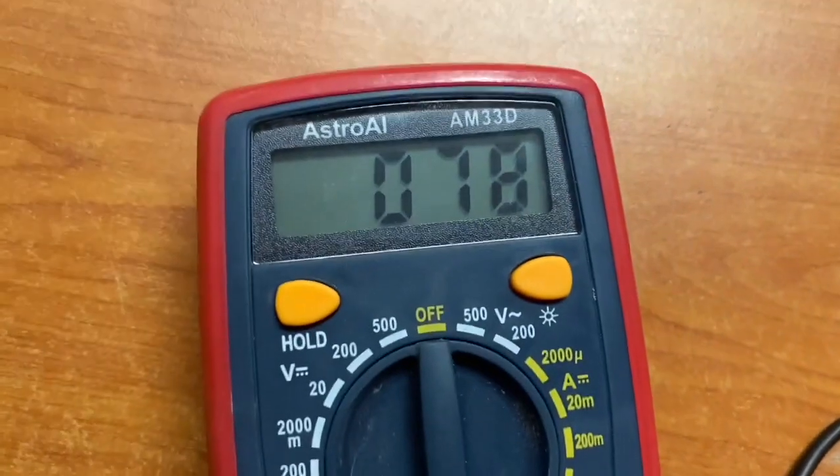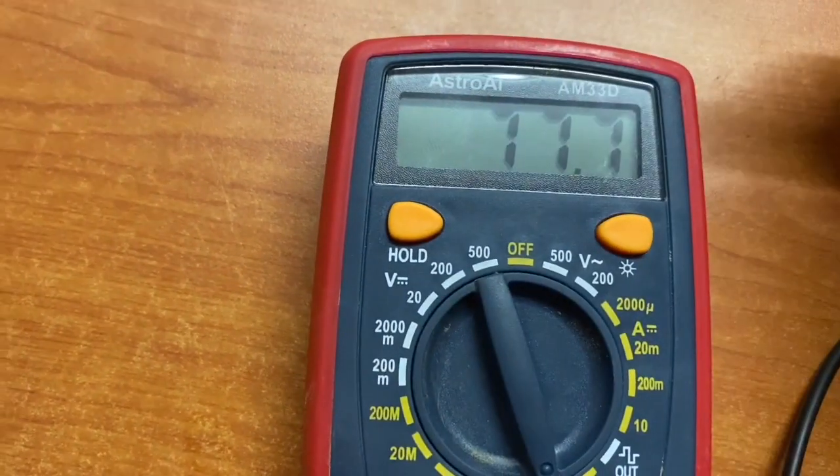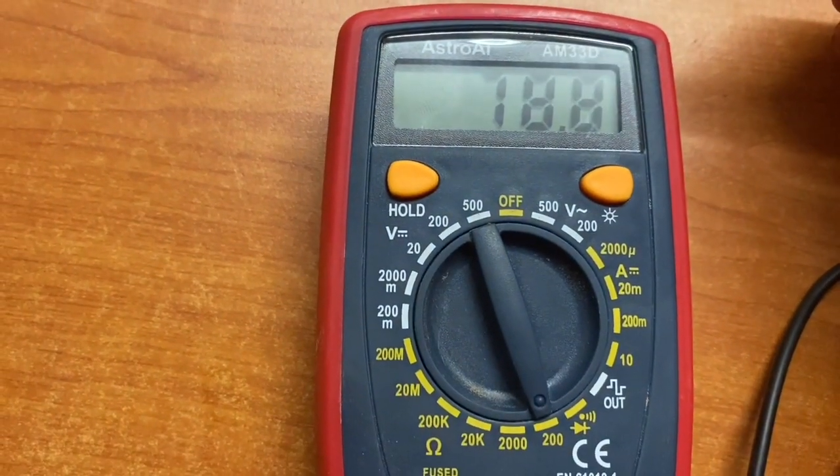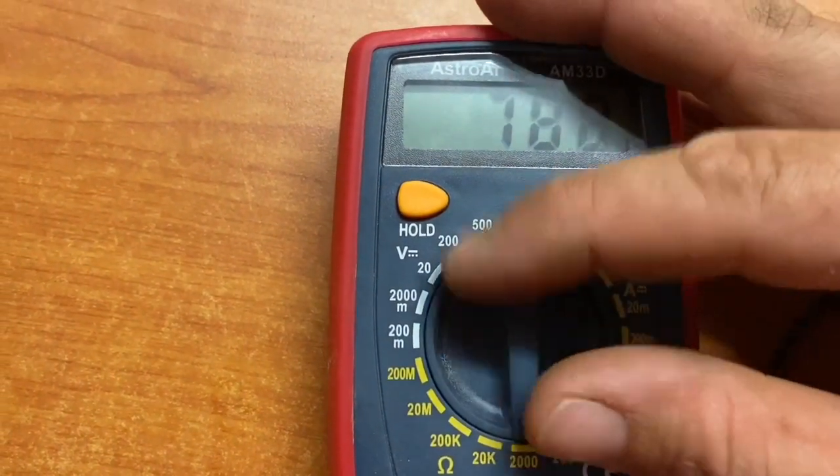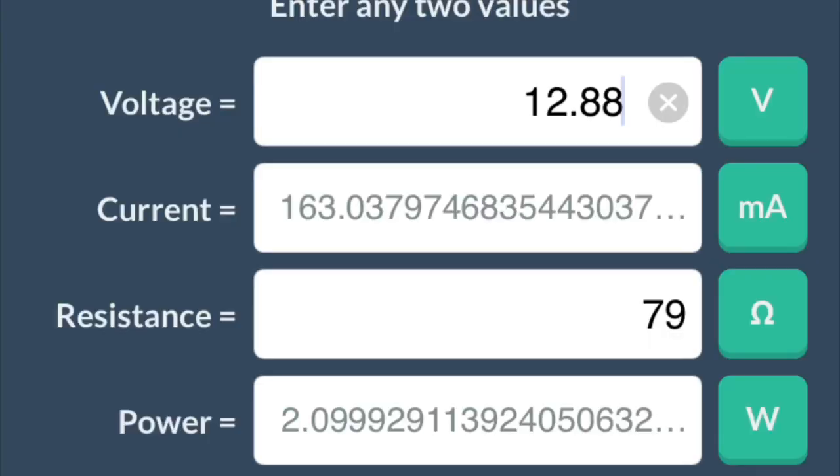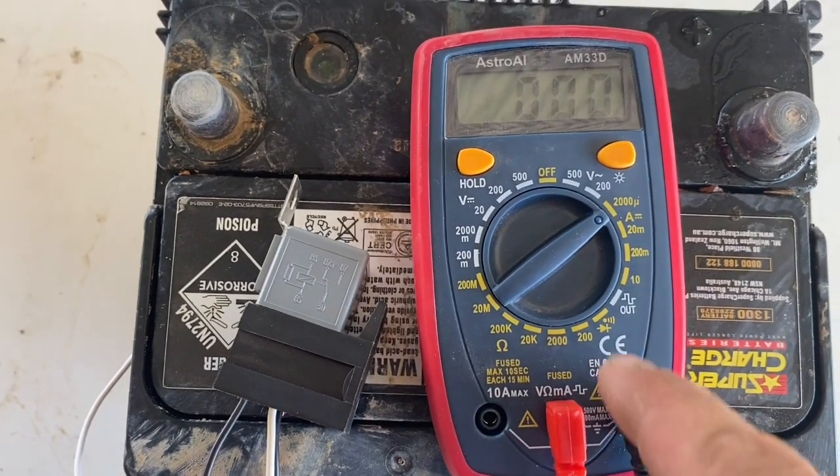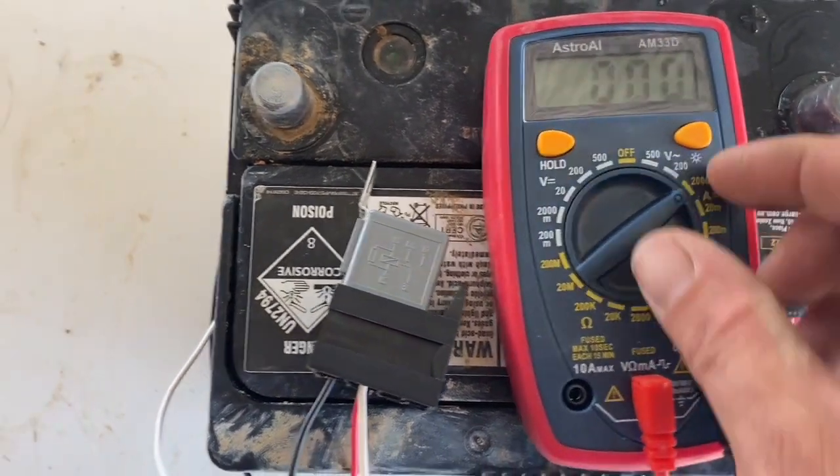So we type 79 ohms into our calculator at 12.88 volts and get 163 milliamps. So that's how much current draw this relay should produce when it latches, and we're going to fact check that now.